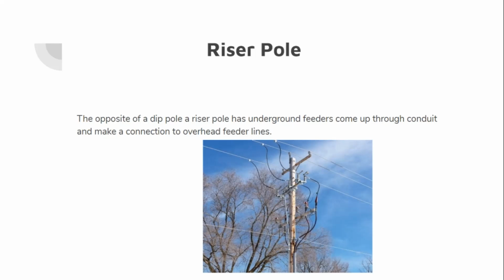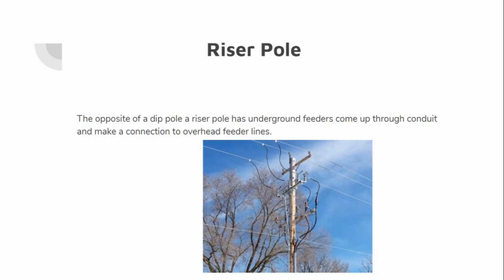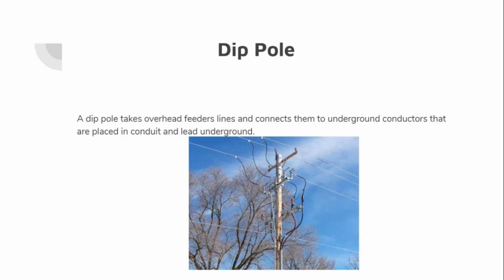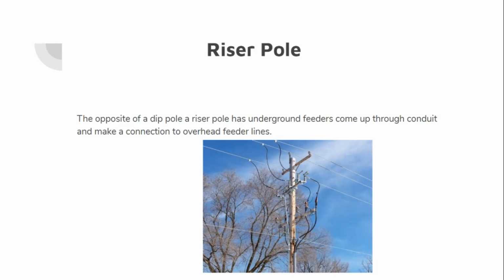All right, riser pole. Now he can get away with the picture this time because this is a feeder circuit. The opposite of a dip pole is a riser pole that has underground feeders coming up through conduit and make the connection to overhead feeder line. The description is kind of decent. Let me go back one. Dip pole takes overhead lines and the feed direction is to underground. That's the description I like to hear. Feed direction is down underground. I'm dipping down. Riser pole is the feed direction is from underground to where?